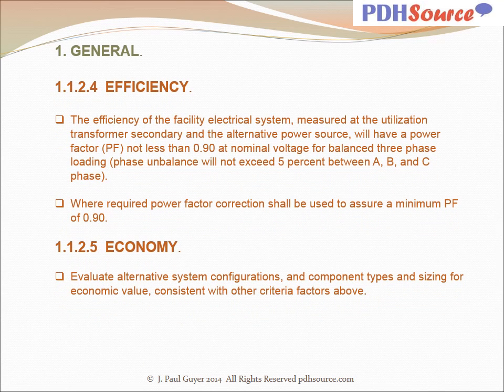The efficiency of the facility electrical system, measured at the utilization transformer secondary and the alternative power source, will have a power factor not less than 0.9 at nominal voltage for balanced three-phase loading. Phase unbalance will not exceed 5% between A, B, and C phase. Where required, power factor correction shall be used to assure a minimum power factor of 0.9. Evaluate alternative system configurations and component types and sizing for economic value consistent with other criteria factors above.